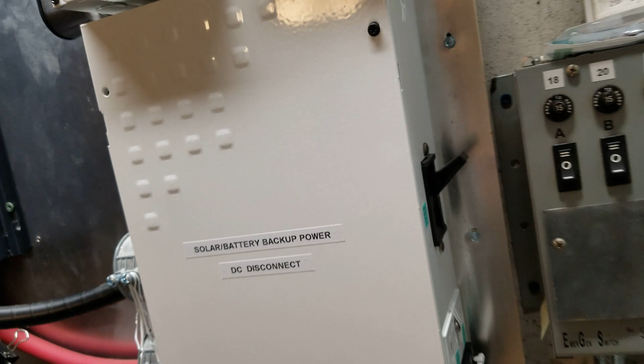So this current surge limiter, when you turn it on, it just makes it so there's a soft start. When you throw the big DC switch for the inverter, it's supposed to do a soft start, and not let the battery's BMS shut it down due to a short circuit it may sense from too much current flowing too quickly. So anyway, that's what that's supposed to do.